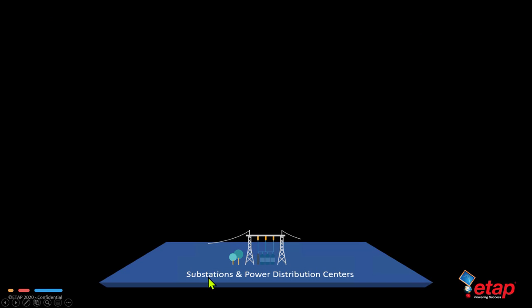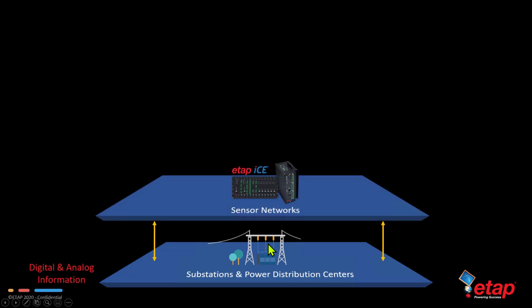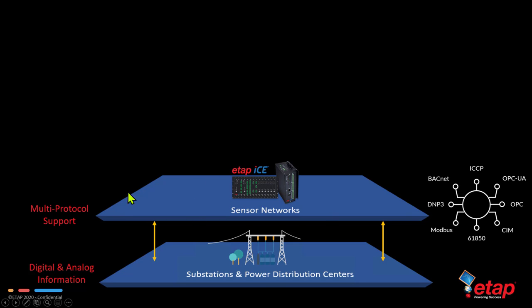eProtect implementation begins with substations and power distribution centers and collecting the digital and analog information from these devices such as relays, transformers, circuit breakers, and so on, using sensor networks and hardware such as ETAP ICE RTUs, the existing relays in the network, DFRs, DDRs, PLCs, and so on. And this data is essentially collected using multi-protocols such as DNP3, Modbus, 61850, or even OPC.